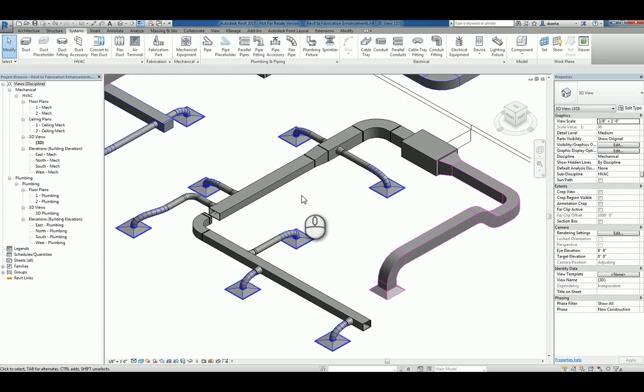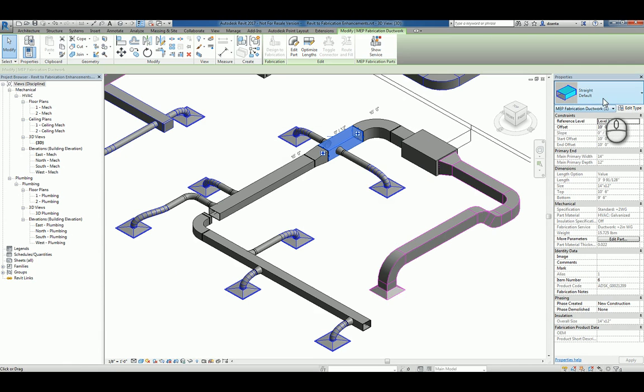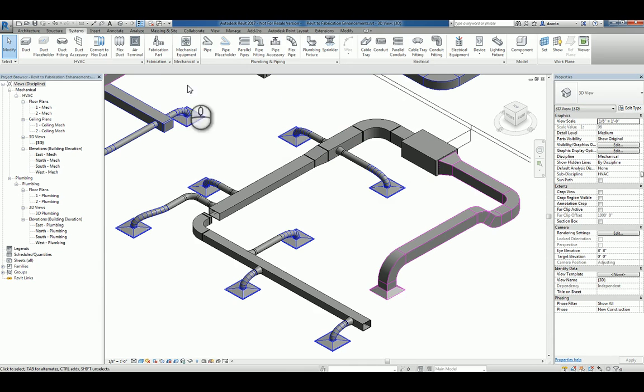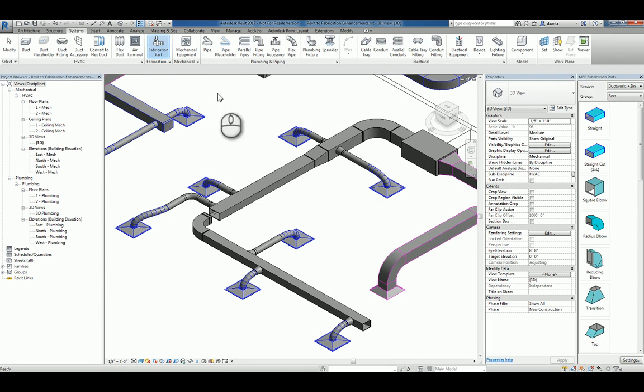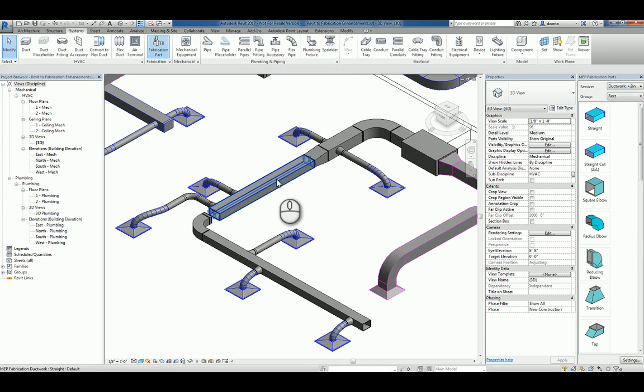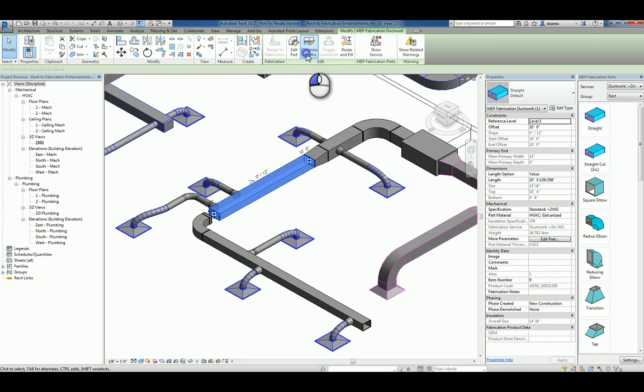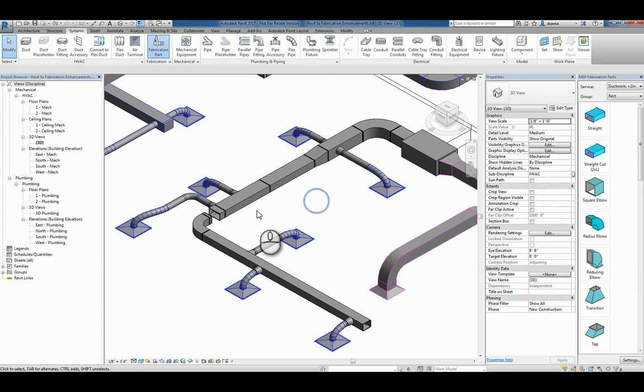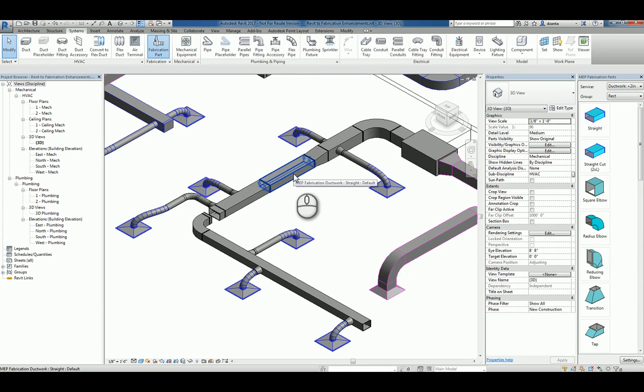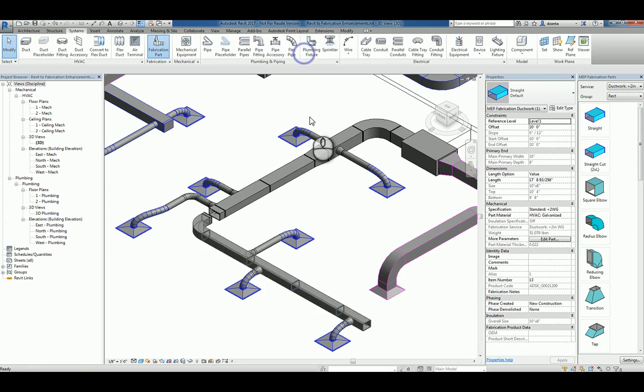And you'll notice, again, these objects are now actual MEP fabrication parts. I can click fabrication part command, and it will open up the MEP fabrication parts panel. It will list the service and the group and the types of objects to be able to work with. I can very quickly and easily select any piece if I need to and click optimize length, and it will adjust them and redesign them to proper manufacturing part lengths. So we'll do that over here as well.